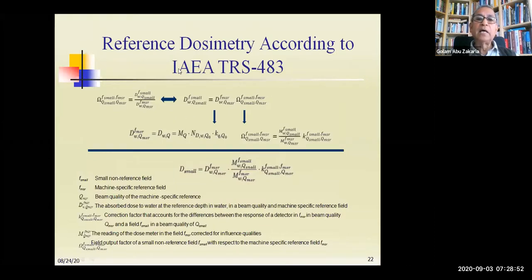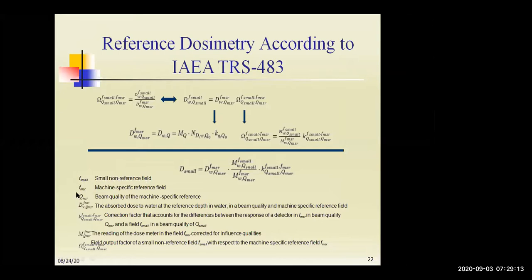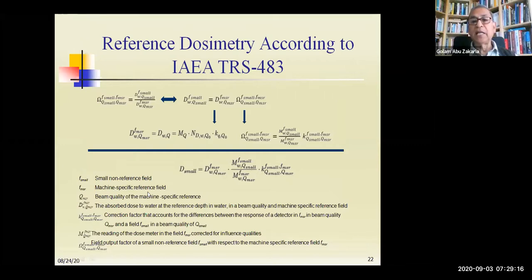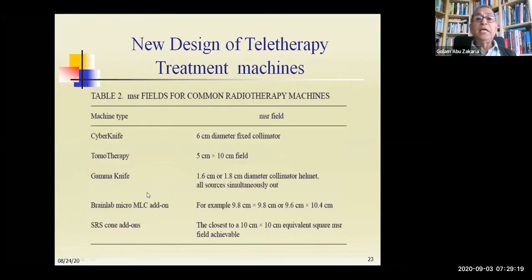So here I just give you once again the same formalism, and you see here are actually different terms. And in the protocol, at the beginning, they are explained very well. You should learn very well, for example, f small, that means the field for the small non-reference field. f MSR, machine specific reference field, like this. So here is a new design of radiotherapy machine. That's why the machine specific reference field: you see here different fields, the maximum field is not 10 by 10. This is our problem, and that's why we have this protocol.